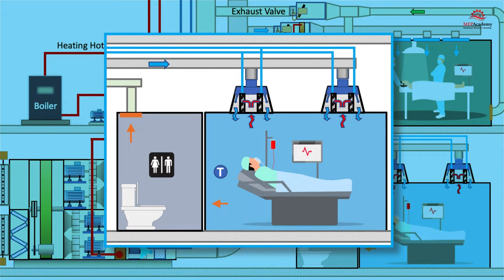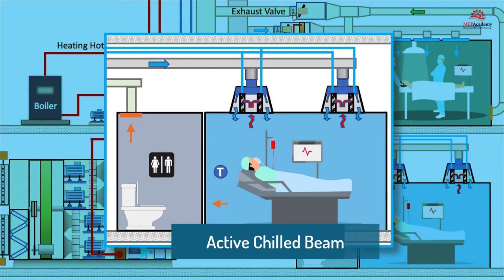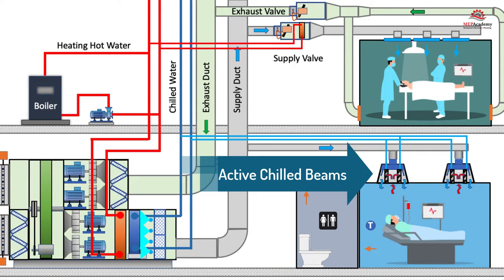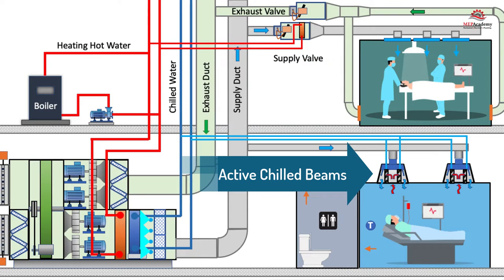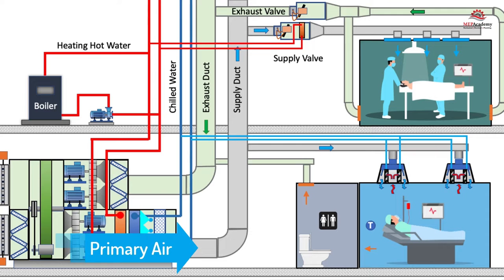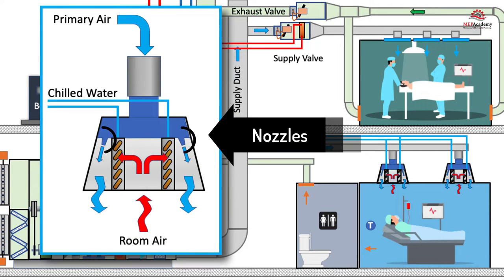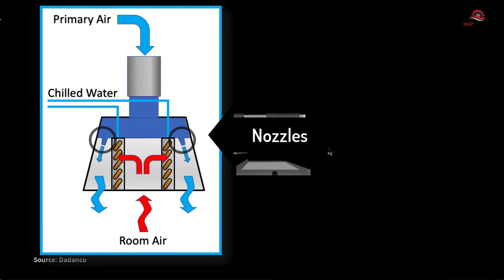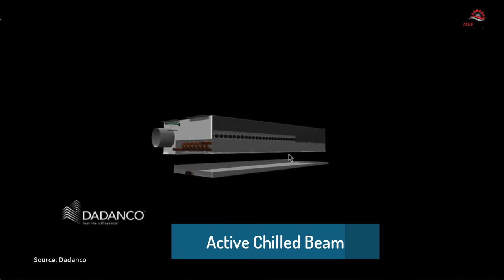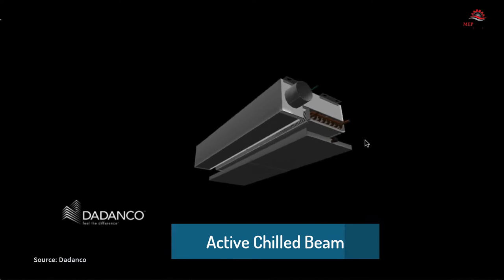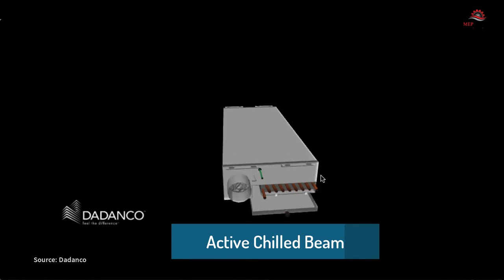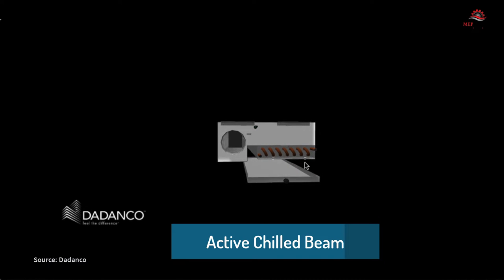Between the two types, the most commonly used is the active chilled beam. An active chilled beam contains one or two coils in a sheet metal housing suspended or recessed within the ceiling. Primary air from an air handler or DOAS unit is connected to the chilled beam, sending air through nozzles that induce airflow from within the space through the coils. The use of primary air from an AHU allows for greater capacities than the passive chilled beam type, which is why active chilled beams are more commonly used.